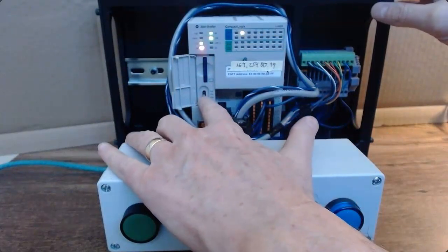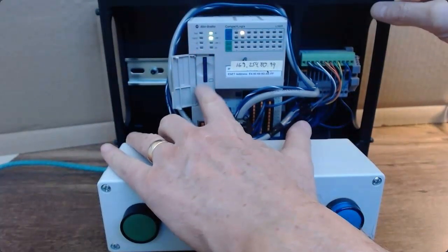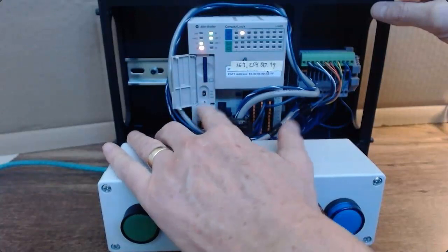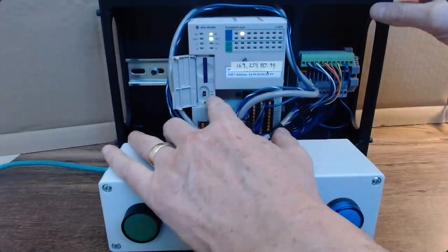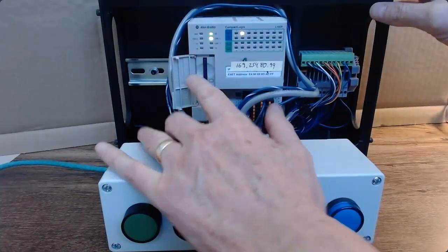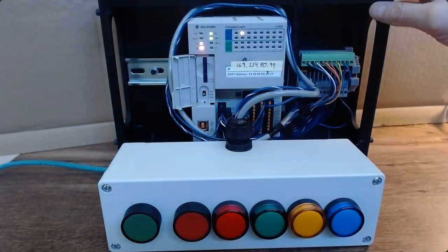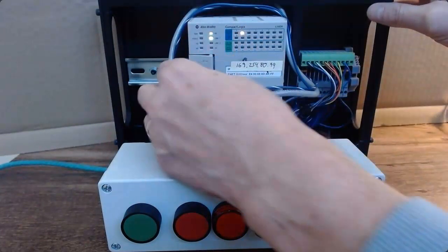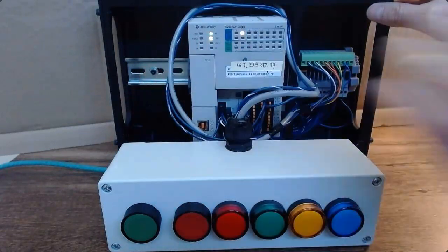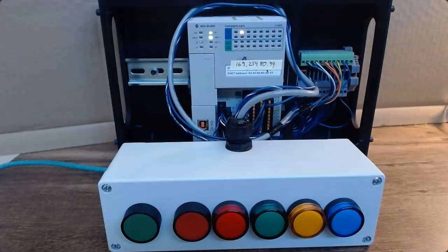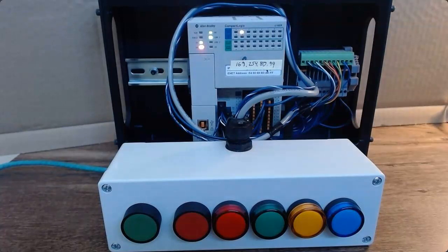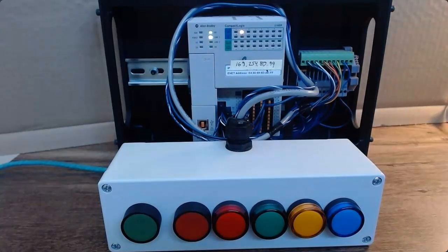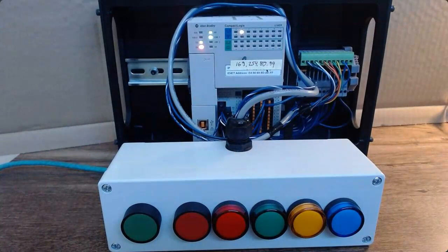And then I raise the switch up into run and bring it back down into rem for remote run, it'll clear the fault. And in this case it clearly does not. Therefore, what I'm going to have to do is I'm going to have to connect with the PLC and investigate the fault closer with the programming device.